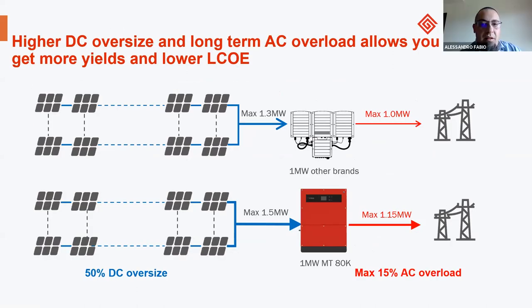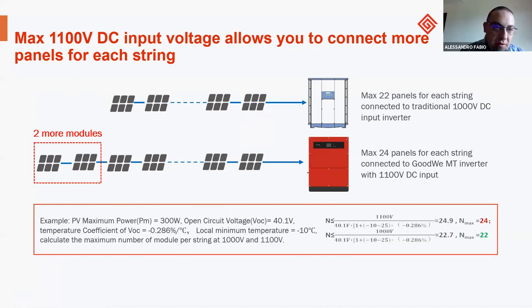About the DC oversize and AC overload, we have the possibility to oversize the DC side by 50%, and the AC side by 15%. This means that you can oversize a part of the plants more than the competitors, for example. So with a smaller inverter, you have more power from the DC side to the AC side. You can see the difference between us and the competitors. With our technology with 1,100 volt DC input voltage, you can put more modules per string. This is also an advantage versus the competitors.